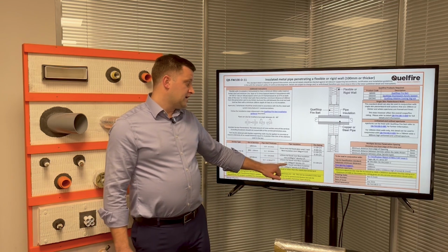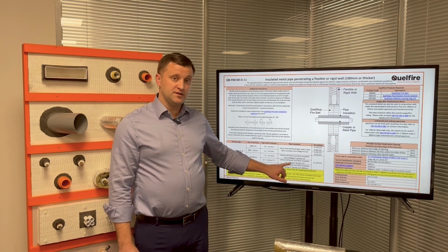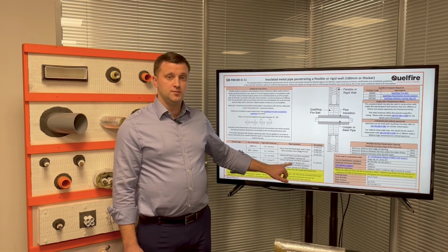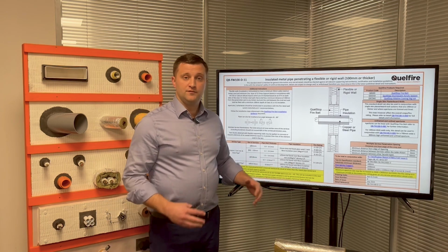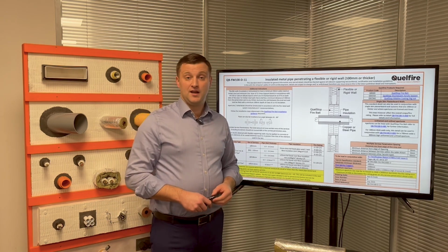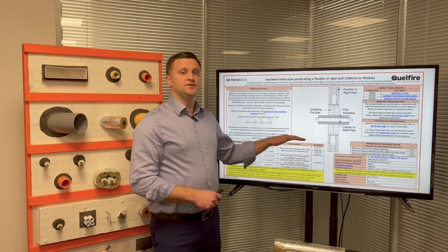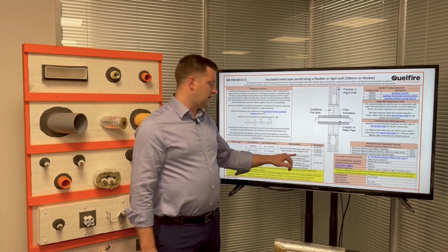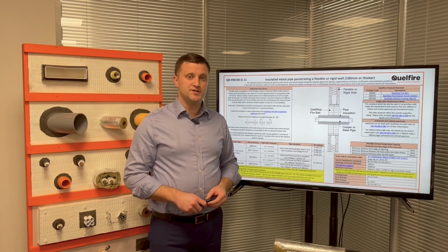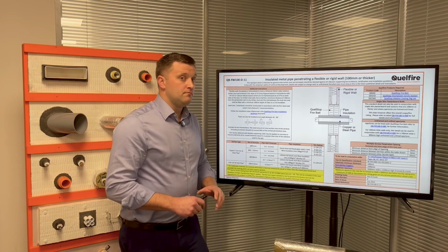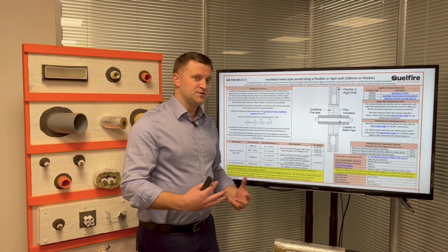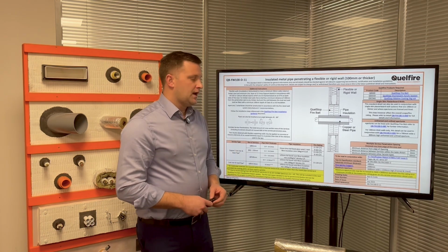So, a minimum density of 90 kilograms per cubic metre would cover things like Paroc Alucoat T. So that could be used as an alternative to other denser brands, which for instance are at 120 kilograms. So hope that clarifies the point about the density.